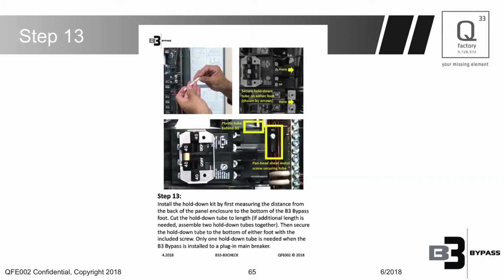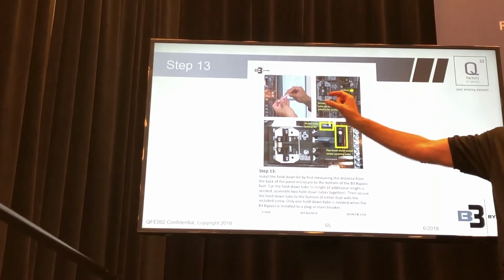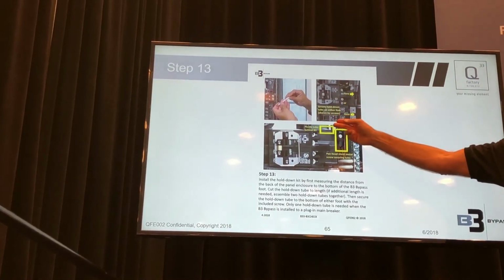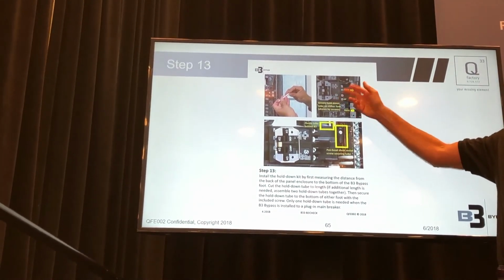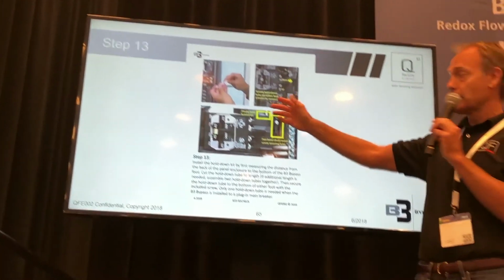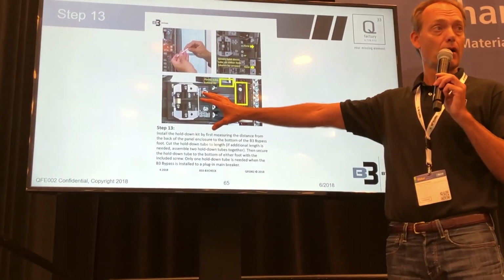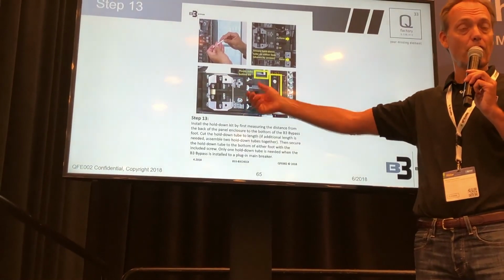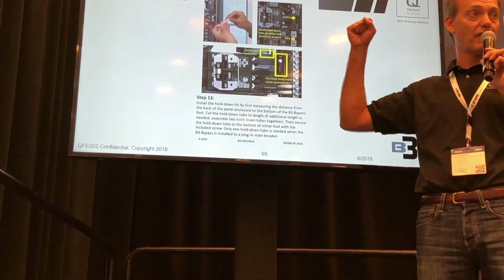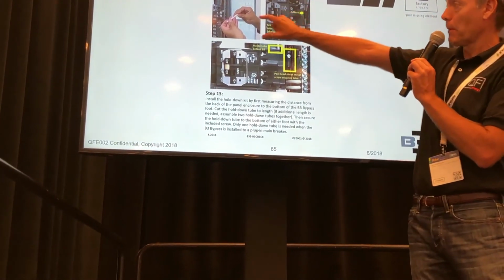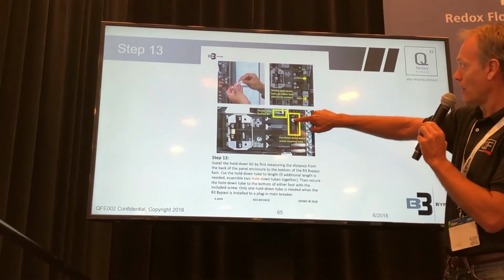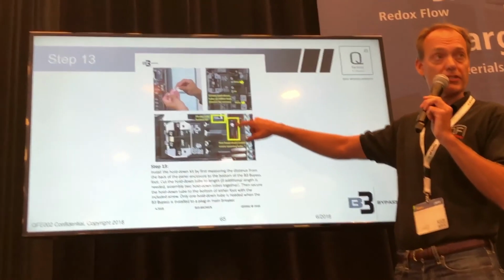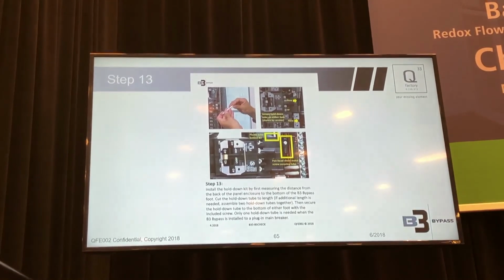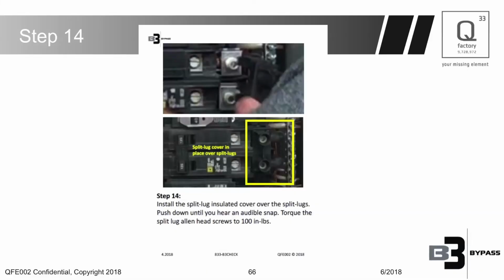Once you do that, we want to make sure that you put a hold down kit in place. We include these little standoffs; cut them to size. We're going to go from the back of the B3 to the back of the panel. The reason for that is, since the B3 is not controlled by the main breaker, if a homeowner turns off the main breaker, they're not going to yank out the B3, because that still is energized. So we have this little hold down kit. It's a little plastic standoff. We have two little screw openings here. You can just screw it right in place to secure it so somebody doesn't pop it out.